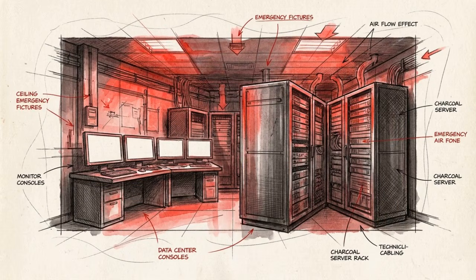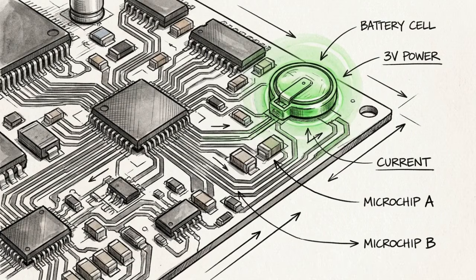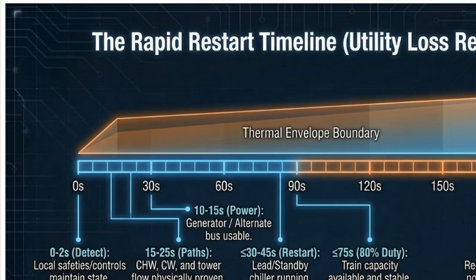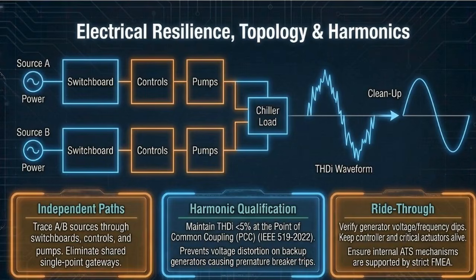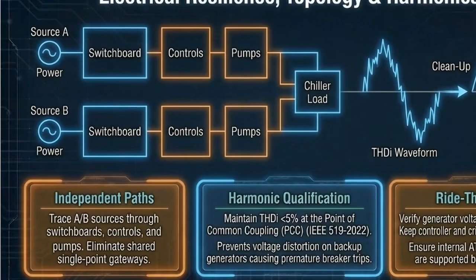In the first 2 seconds, alarms cascade across the facility, but local safeties and controllers must rely on their onboard power to forcefully maintain their logic state and prevent a full memory wipe. Looking at the rapid restart timeline, we see that between the 10 and 15-second marks, the backup generators spin up to full speed, and the alternate bus power finally becomes usable for the mechanical systems. This diagram of electrical resilience illustrates how that power is delivered. It requires independent A and B power paths terminating directly into the chiller load, completely eliminating any shared single-point control gateways. Restoring power is not enough.